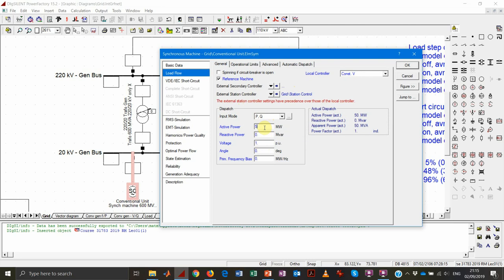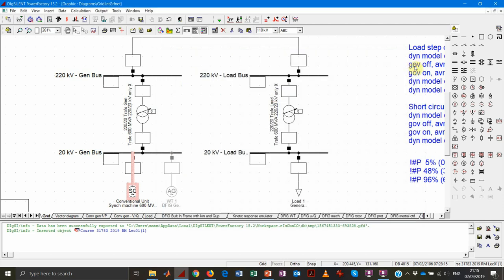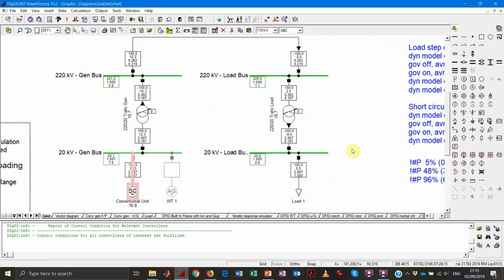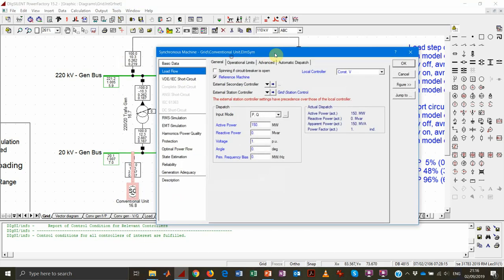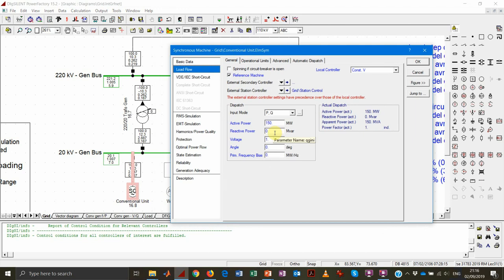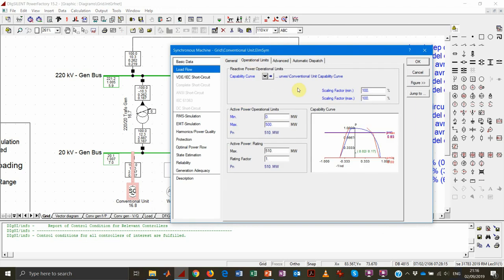As mentioned last time, for the active power value, PowerFactory will set it automatically according to what is necessary to balance consumption and losses in the system. Another important feature is the tab characterizing the operational limits of our machine. We can see that our machine is allowed to produce down to zero megawatt — so it can be completely deloaded — and up to 500 MW, which is very close to the nominal rating of the generator.